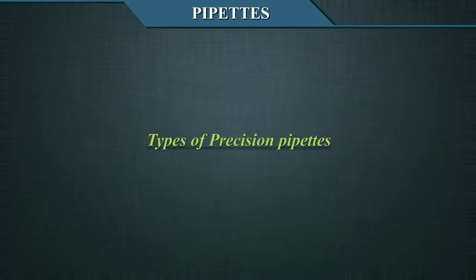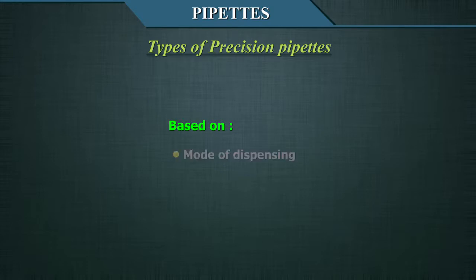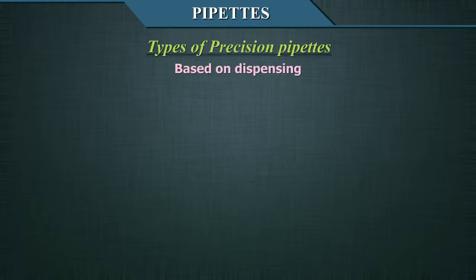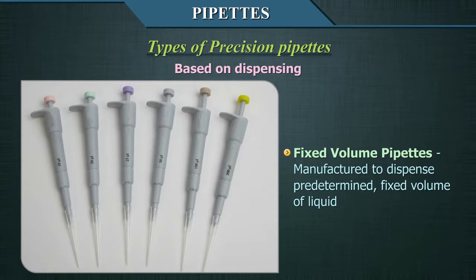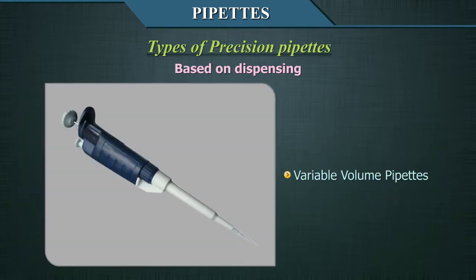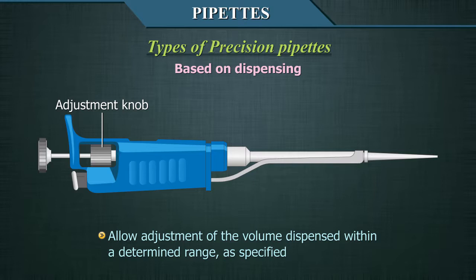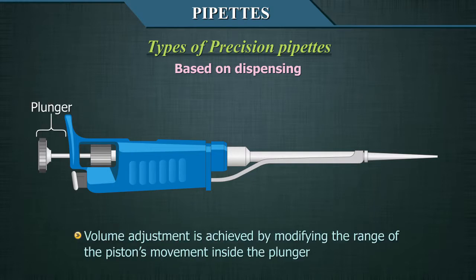Types of precision pipettes can be classified based on mode of dispensing and mechanism of action. Based on dispensing, they are further divided into fixed volume pipettes or variable volume pipettes. The fixed volume pipettes are manufactured to dispense a pre-determined fixed volume of liquid. The variable volume pipettes allow adjustment of the volume dispensed within a determined range, achieved by modifying the range of the piston's movement inside the plunger.